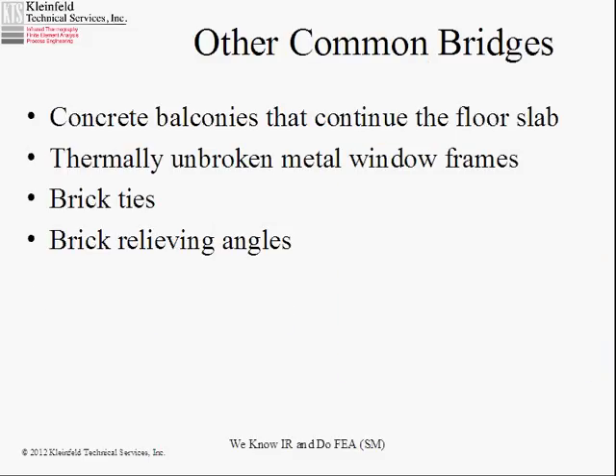Other common bridges would be concrete balconies that are contiguous with the floor slab. In an apartment building with balconies every floor all the way around, every one of those is releasing heat because the floor inside is warm, connected to the balcony outside directly, and the balcony is warmer than it should be if it could be isolated with a thermal break. Thermally unbroken metal window frames are the ones people think of immediately. Metal window frames without thermal breaks are a disaster from the energy standpoint. Brick ties, brick relieving angles — which are angle iron every one to two floors holding the bricks up — are tied back into the structural wall and represent a bridge through that metal path.